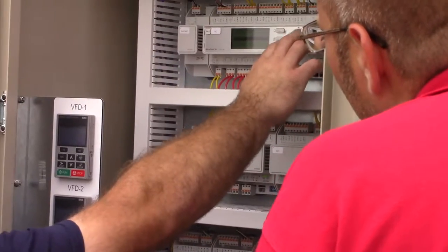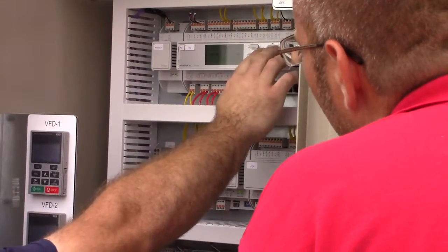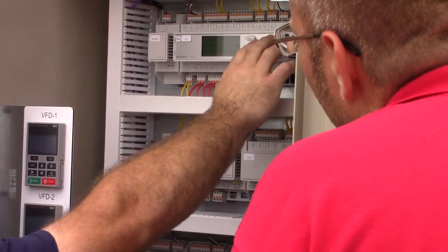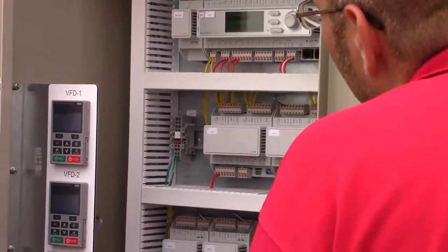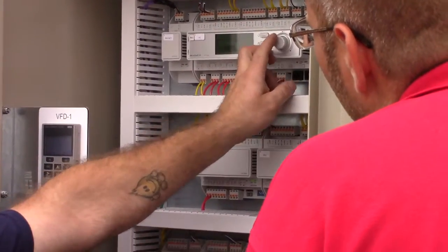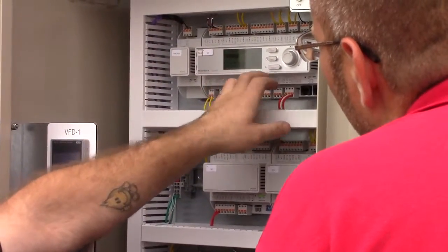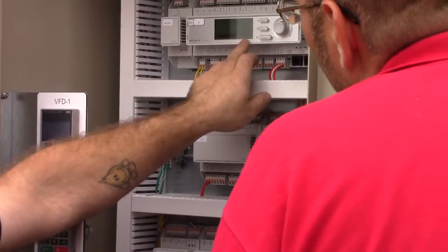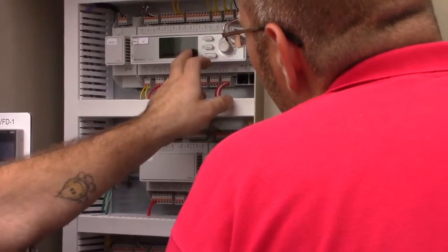Basically, if you start off with the password, it'll give you all the menus available, 63. Every time I do it, I just press it for enter to enter the number, and then 63 again. And then I have full menu options. So view set, I can go into the temperatures menu for the water side, see my leaving water, entering water, a couple other points, delta T, the set point it's currently running on, pull down rates, outside temperatures.